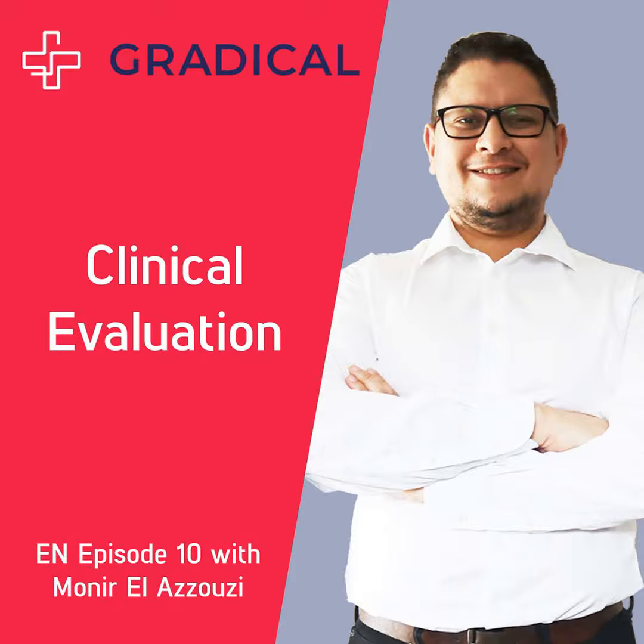There is a specific document that can really show that to you, which is the MedDev 2.7/4 revision 1, which is mainly the clinical evaluation guideline on how to do all the steps that we just talked about. And for those who may be asking, this clinical evaluation can take maybe 2 to 3 months to compile. Because as I've said, you have all the literature to read and understand, and then you compile all this together, etc. It can really take some time. If it's a simple device, maybe it's less time, but if it's a really complex device, it can take a lot of time.